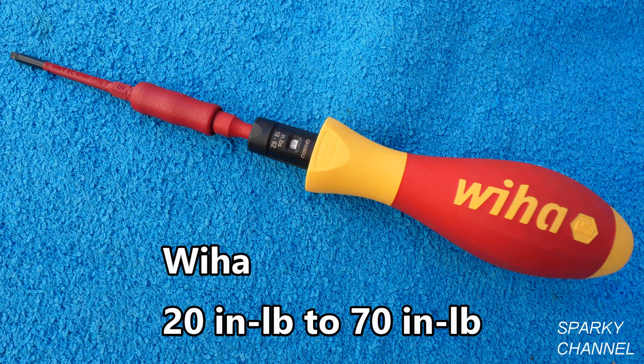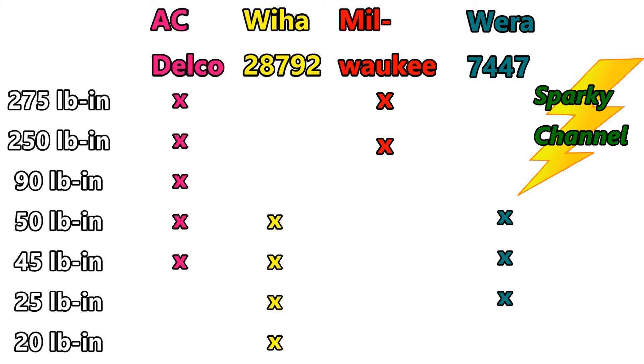Here's a chart I've made up. On the left-hand side you see all the torque specifications found in the load center I showed you. The AC Delco covers 275, 250, 90, 50, and 45 inch-pounds, making it a very valuable torque wrench for this panel. The Wiha 28792 covers 20, 25, 45, and 50 inch-pounds.